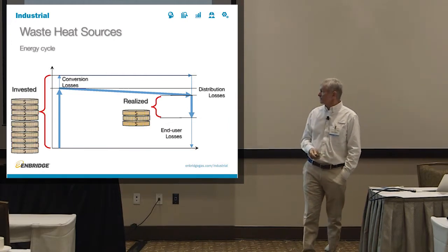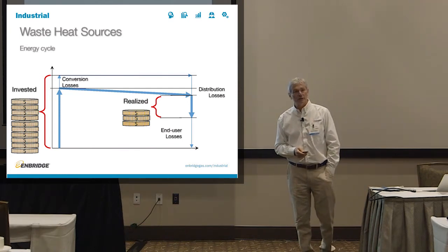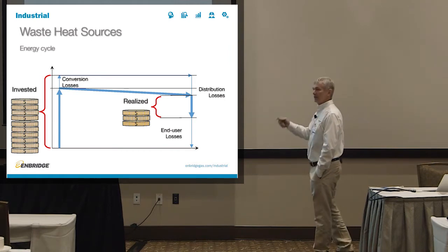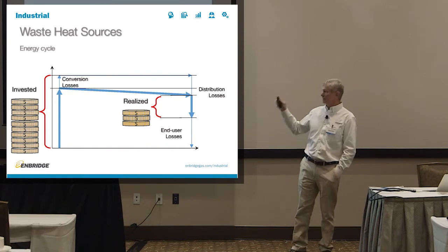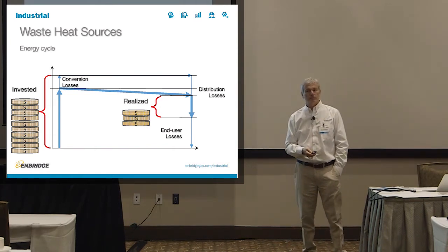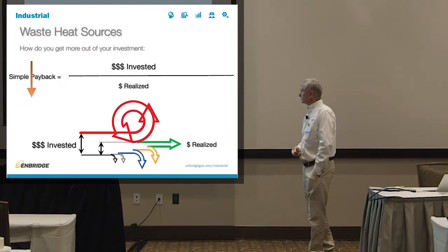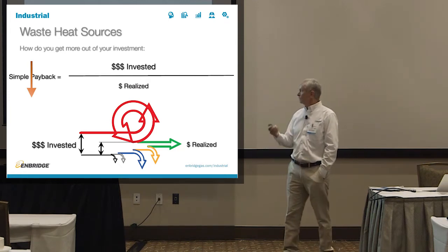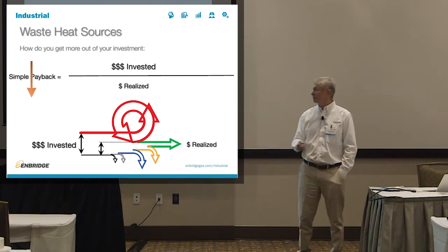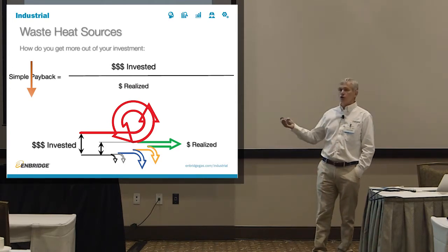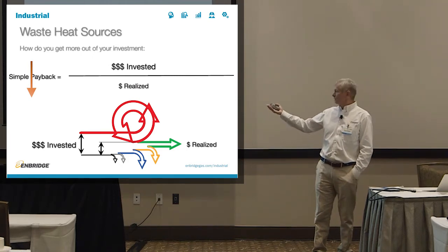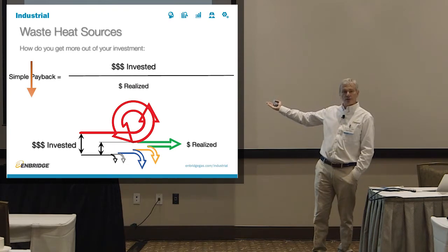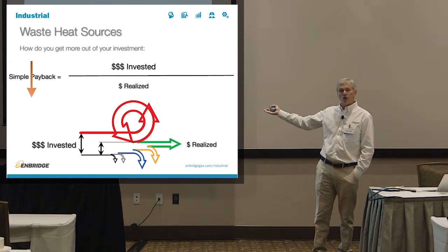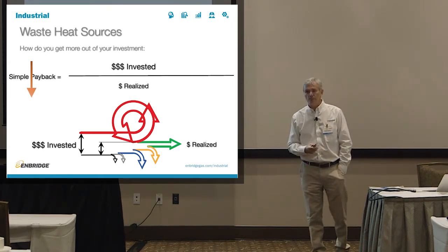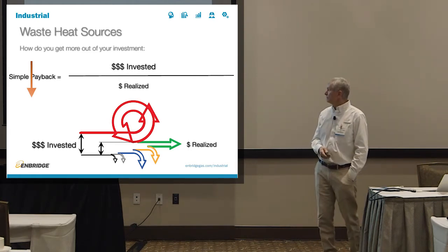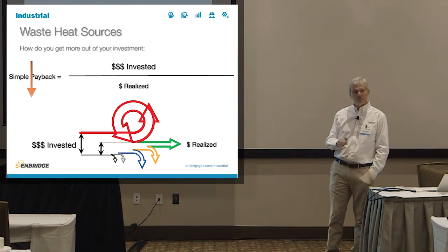One other way of looking at this is, if this is the money you invested to generate the energy that you needed in your facility, this is the amount of money you would actually realize as your benefit. The rest is waste. You just throw it out. So how do you get more out of that? If you look at the simple payback, money invested divided by money realized, and if you look at all the sources of energy that you are using in the facility, you have all the energy on the input. The green arrow shows the energy that you actually get out of it. All the other arrows show the losses along the way. If you can take some of those losses and put them back into the input, you would reduce the money that you need to invest into the facility, and you would improve your simple payback. It's as simple as that.